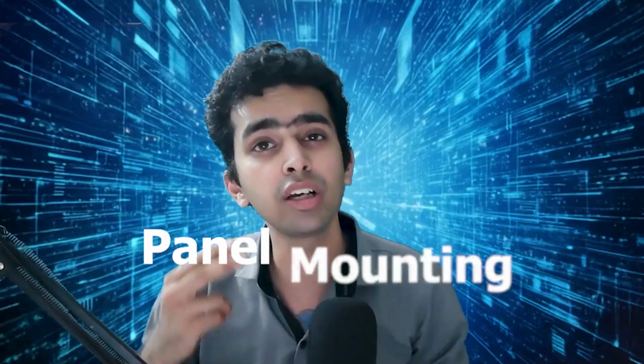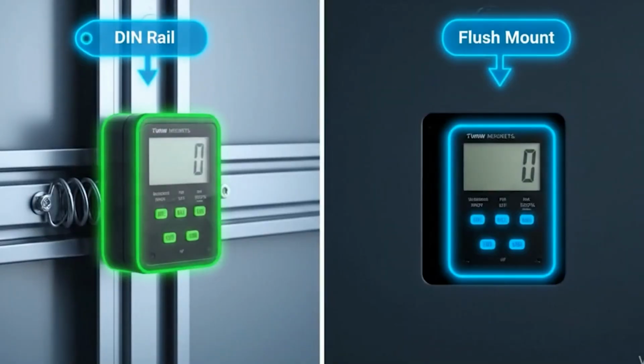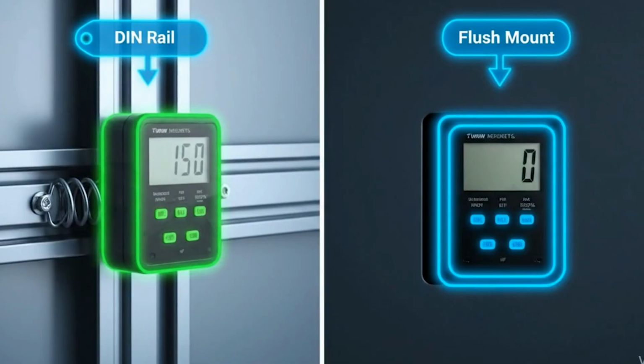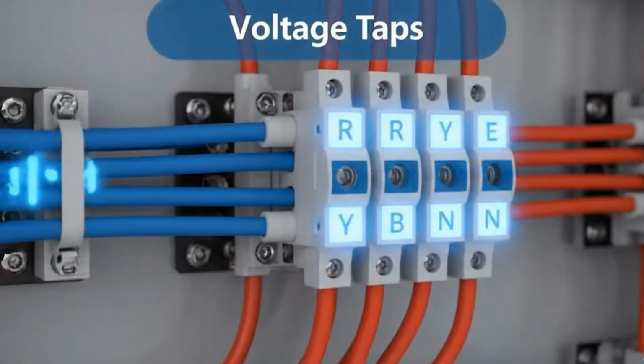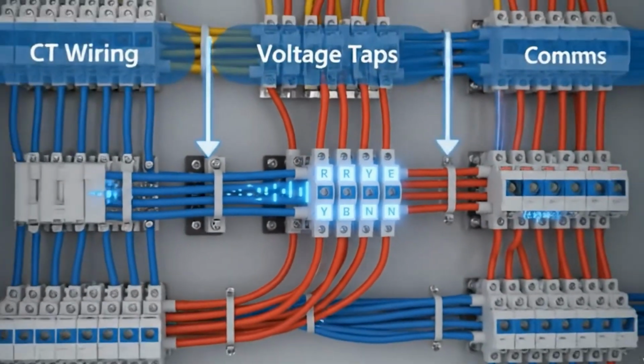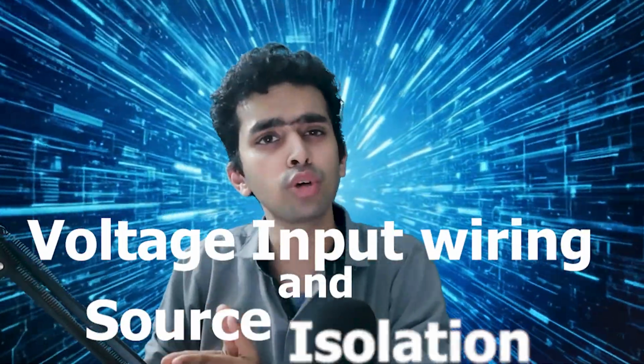Next one is panel mounting and space planning. Check your electrical panel's form factor, whether it is DIN-rail mounting or needs a flush-mounted meter. And confirm you have enough space for wiring, voltage taps, and communication cables, specifically in compact power panels. Third one is voltage input wiring and source isolation. Each power source, grid or generator or solar, must have a separate voltage input wiring to the meter. And this is very important. Always use proper protection devices like breakers or isolators to avoid accidents or damage during maintenance.